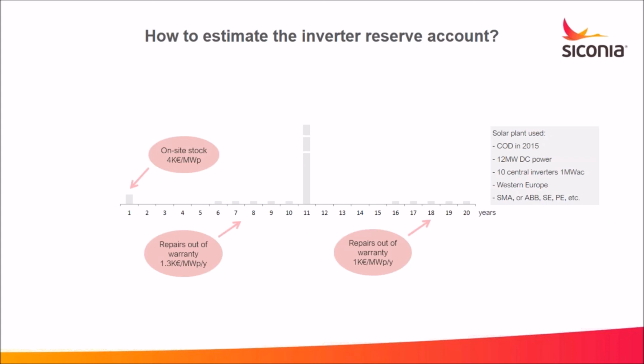Around year 11, we will need to consider the replacement of the inverter. Remember, we have no service contract with the manufacturer. The inverter is probably obsolete by that time, and some spare parts would have become much more expensive and even not available in the market anymore, so repair at some point won't be an option.